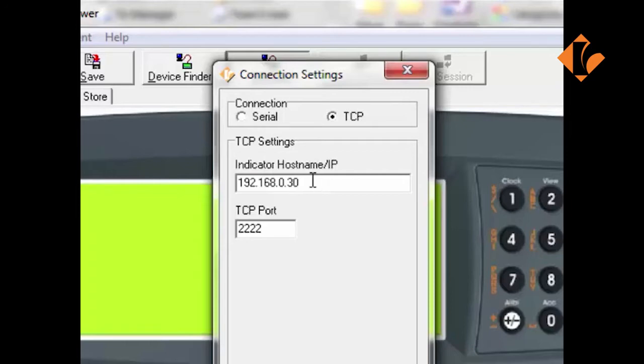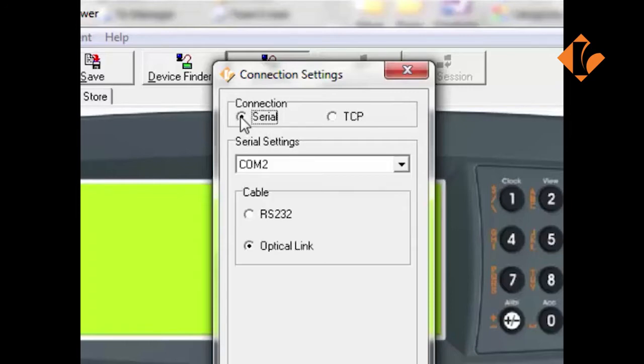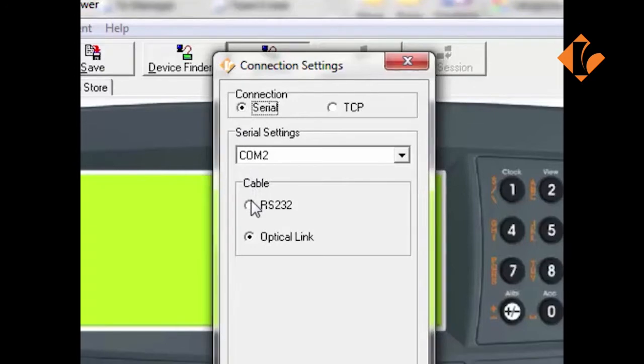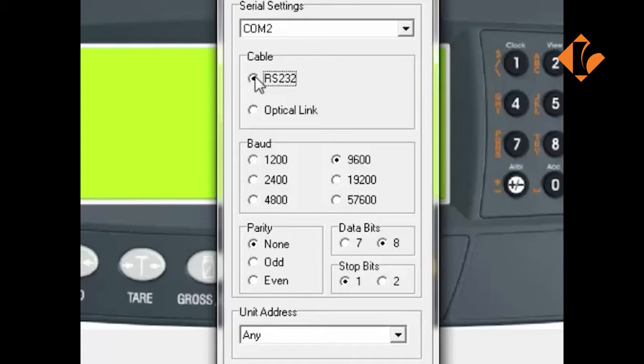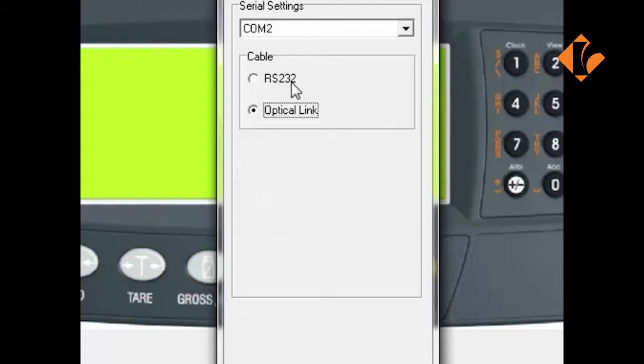For this series, we will be looking at the serial connection. Click the Serial button and you will notice there is RS-232 and Optical Link. The RS-232 allows for the DB9 or 25 pin connection to RS-232 ports, typically on tower PCs. The default settings are 9600, 8, none and 1, which reflect the default settings within the Rinstrum indicator, so there should be no need to change these.